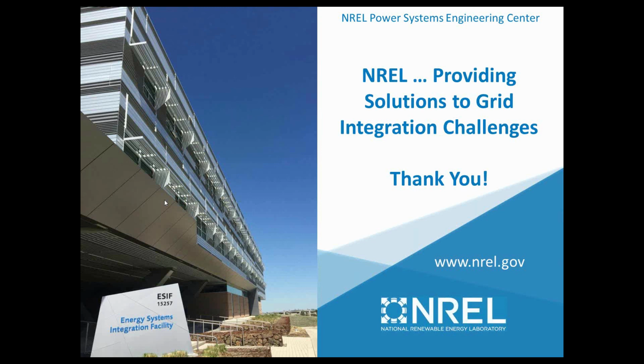The challenges that I've heard that people have with it is potentially, it's something that would have to be embedded in distributed generation, so it's adding a little bit of cost, but obviously probably much less than a dedicated fiber line. And you'd have to make sure that the utility really is able to provide that signal without causing undue distributed generation trips, because now everything has a very permissive signal to be connected, and so potentially you may have some issues with the ability to massively trip everything off simultaneously. So there are some things that people need to think about.